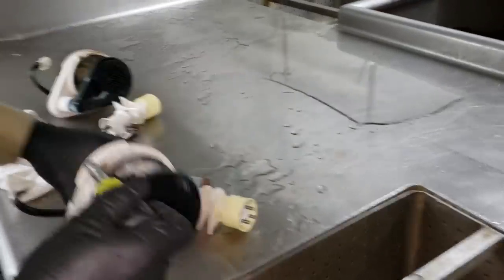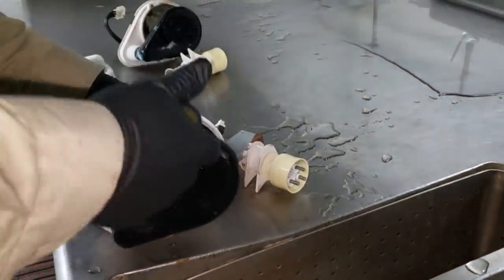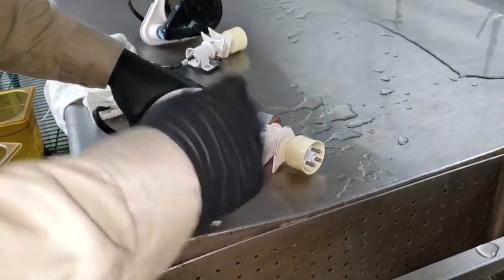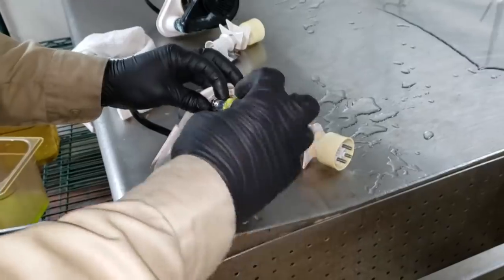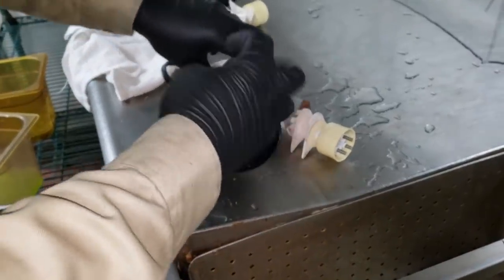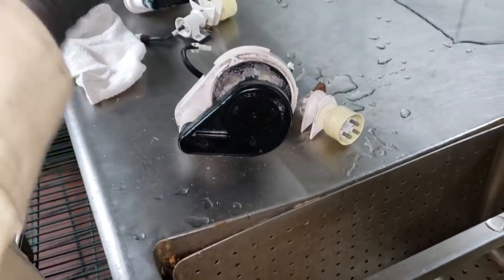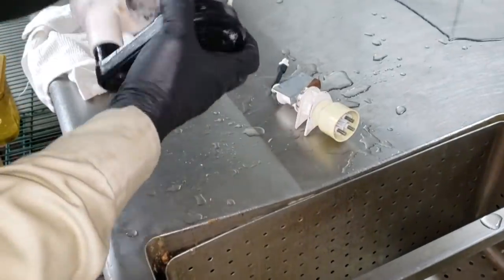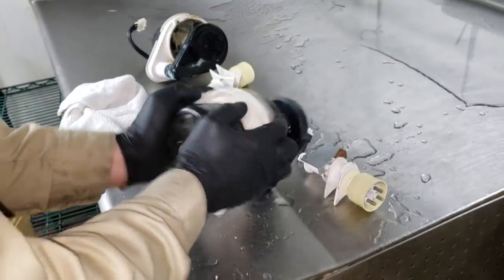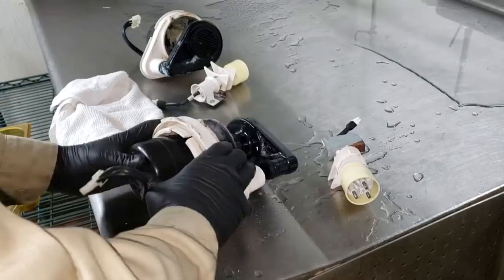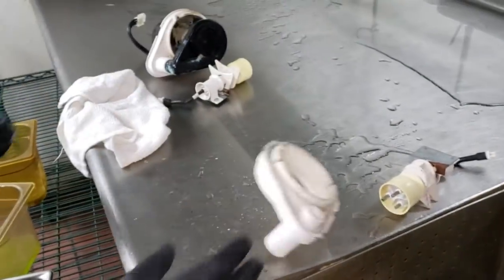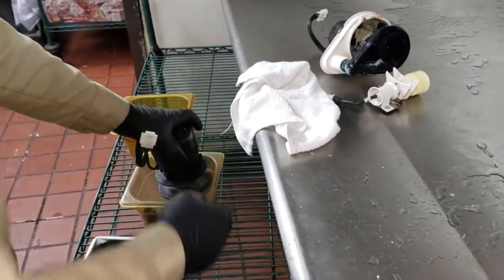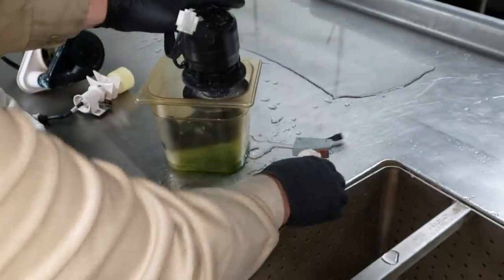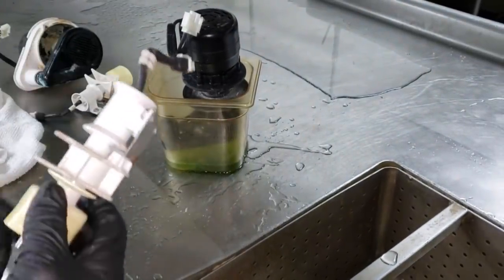Okay, so on the bottom of these guys is a little set screw. We're going to take that set screw off. Again, not losing anything. All my screws are going in one pan, not getting lost, okay? Once we pull that set screw off, this guy pops off this way, up and over. Now we have the water pump with the pan filled up with water and ice machine cleaner, and it can't tip over, so that's why we use that pan.